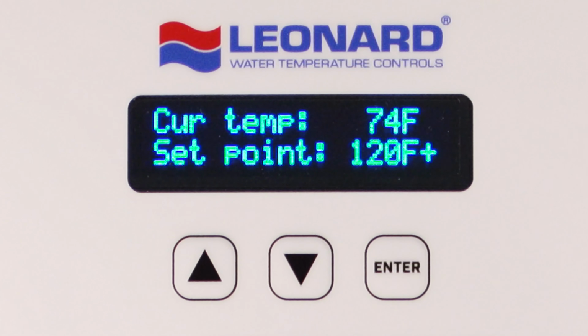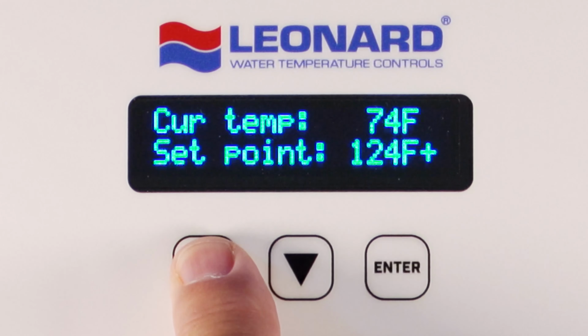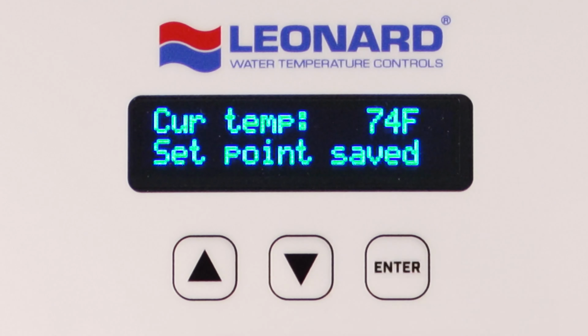Temperature is easily adjusted by pressing the Enter key and pressing the up and down keys to adjust temperature up or down. When the desired value is reached, pressing the Enter key will store the new set point temperature the valve will target, and a message stating that the set point has been saved will be displayed. If no new temperature is saved, the screen display will revert back to the home screen after approximately 10 seconds, and the set point will remain unchanged.